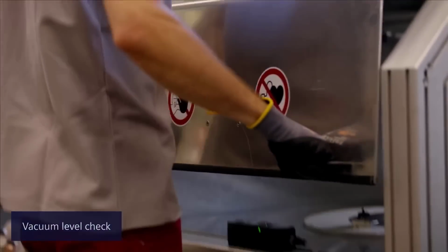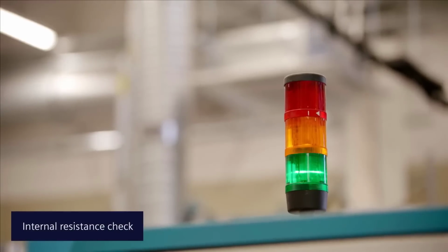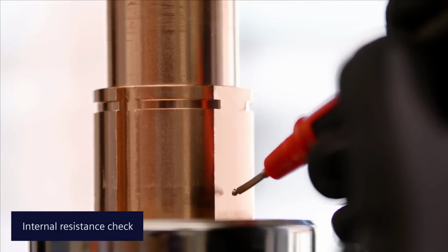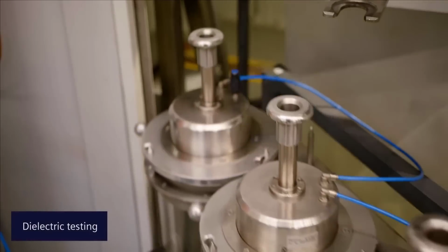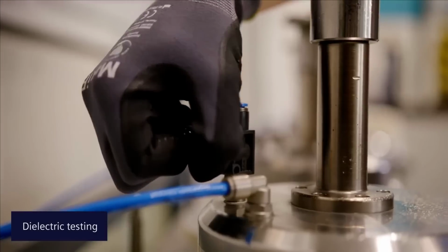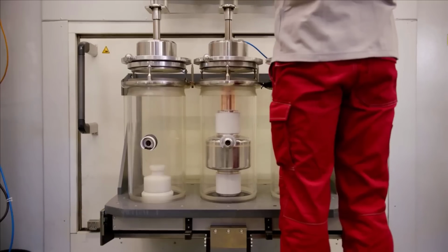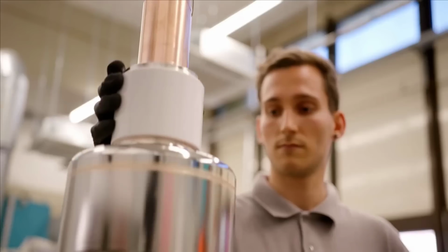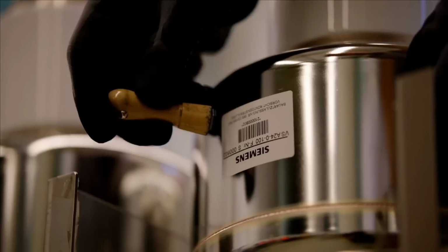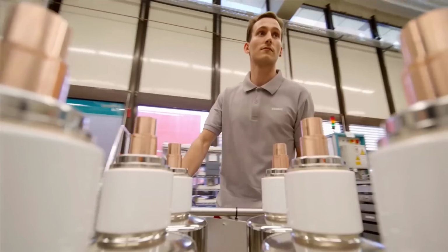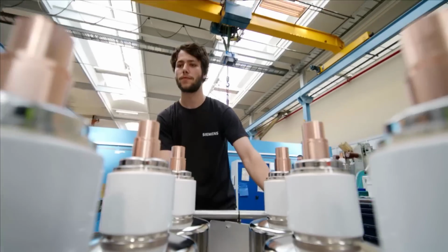Vacuum level check ensures optimal vacuum pressure for interrupter performance. During internal resistance check, dielectric testing, the interrupter's internal resistance is measured and dielectric strength is verified, ensuring it withstands high voltage conditions and operates reliably.